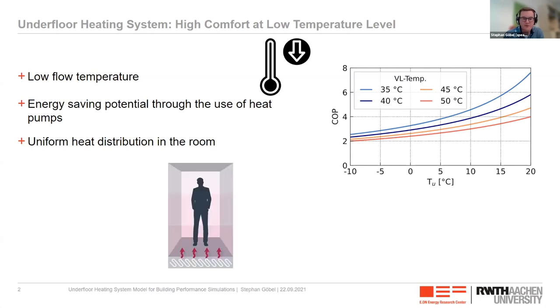Furthermore, we have a uniform heat distribution in the room, which is good in terms of mold prevention, air quality, and comfort. On the other hand, we have an inert system with long response times, which is not easy to control, especially during dynamic days like swing days with high solar radiation.